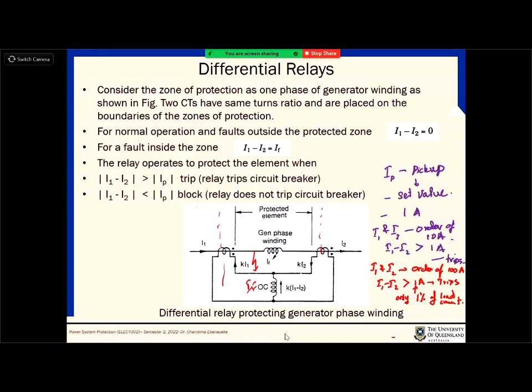Now look at the 10 amp one. If you set 1 amp as the operation current, then what is the percentage? 10%, right? Pick up 1 when the load current is 10, but my pickup current, which is the difference we are now looking at, is 10% of the load current. What do you think? Is it too high? 10%? Let's say what happens when the current is 1% of the load current. Relay won't operate.